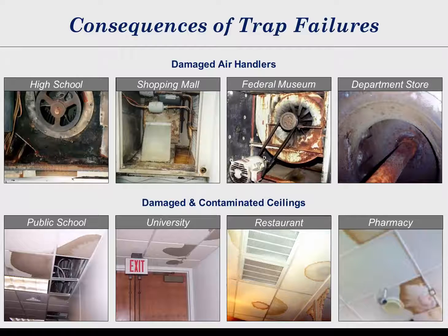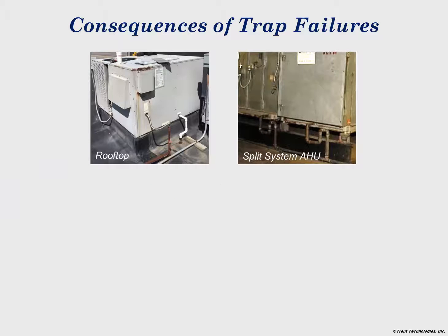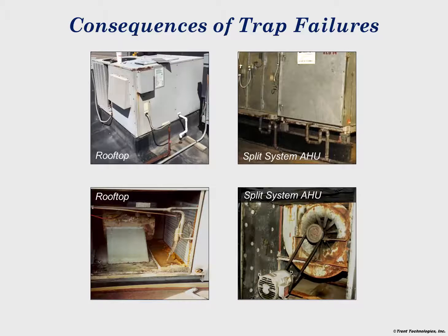The destruction and health threat caused by failed condensate drain systems are extensive. Conditions like depicted here are common and widespread. The wetted surfaces cause corrosion and provide a fertile growth place for contaminating organisms that result in costly property damage and significant health threats. The cause of these conditions are not readily visible to the building owner or manager, so the need to address the situation may not be apparent. Typically what they see during operation are units like the one shown in these photographs. Only when the cabinet is open can the damage be revealed, as shown in these photographs.